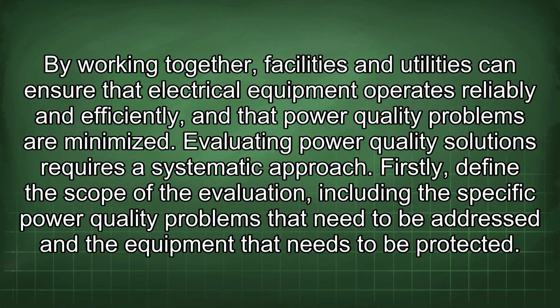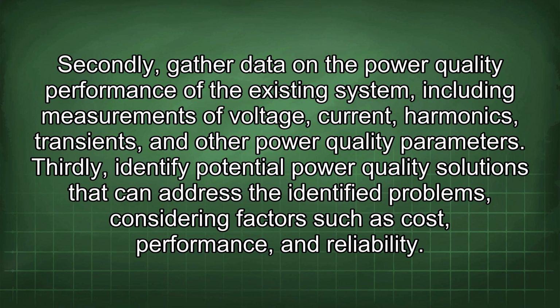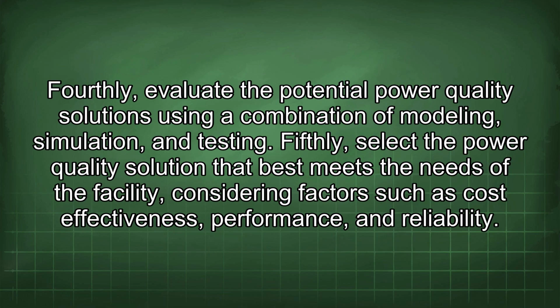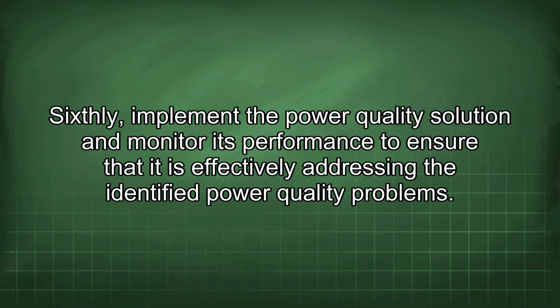Evaluating power quality solutions requires a systematic approach. Firstly, define the scope of the evaluation, including the specific power quality problems that need to be addressed and the equipment that needs to be protected. Secondly, gather data on the power quality performance of the existing system, including measurements of voltage, current, harmonics, transients, and other power quality parameters. Thirdly, identify potential power quality solutions that can address the identified problems, considering factors such as cost, performance, and reliability. Fourthly, evaluate the potential power quality solutions using a combination of modeling, simulation, and testing. Fifthly, select the power quality solution that best meets the needs of the facility, considering factors such as cost effectiveness, performance, and reliability. Sixthly, implement the power quality solution and monitor its performance to ensure that it is effectively addressing the identified power quality problems.